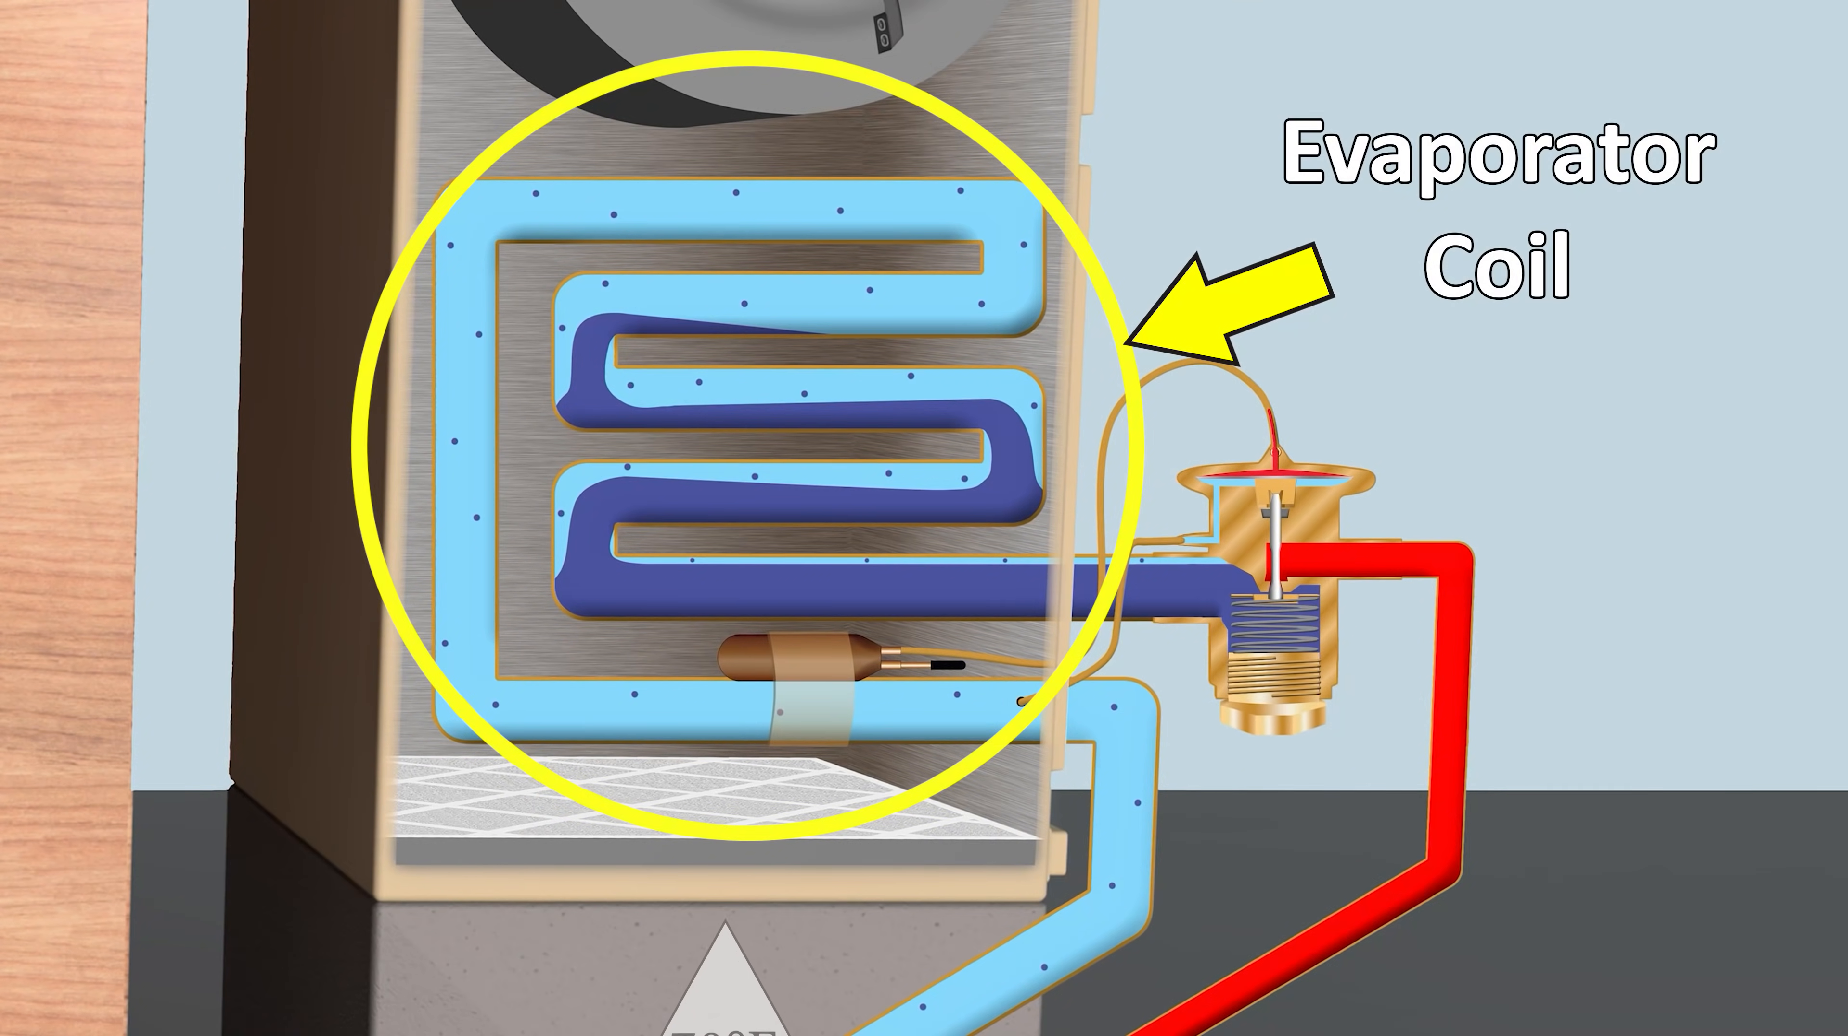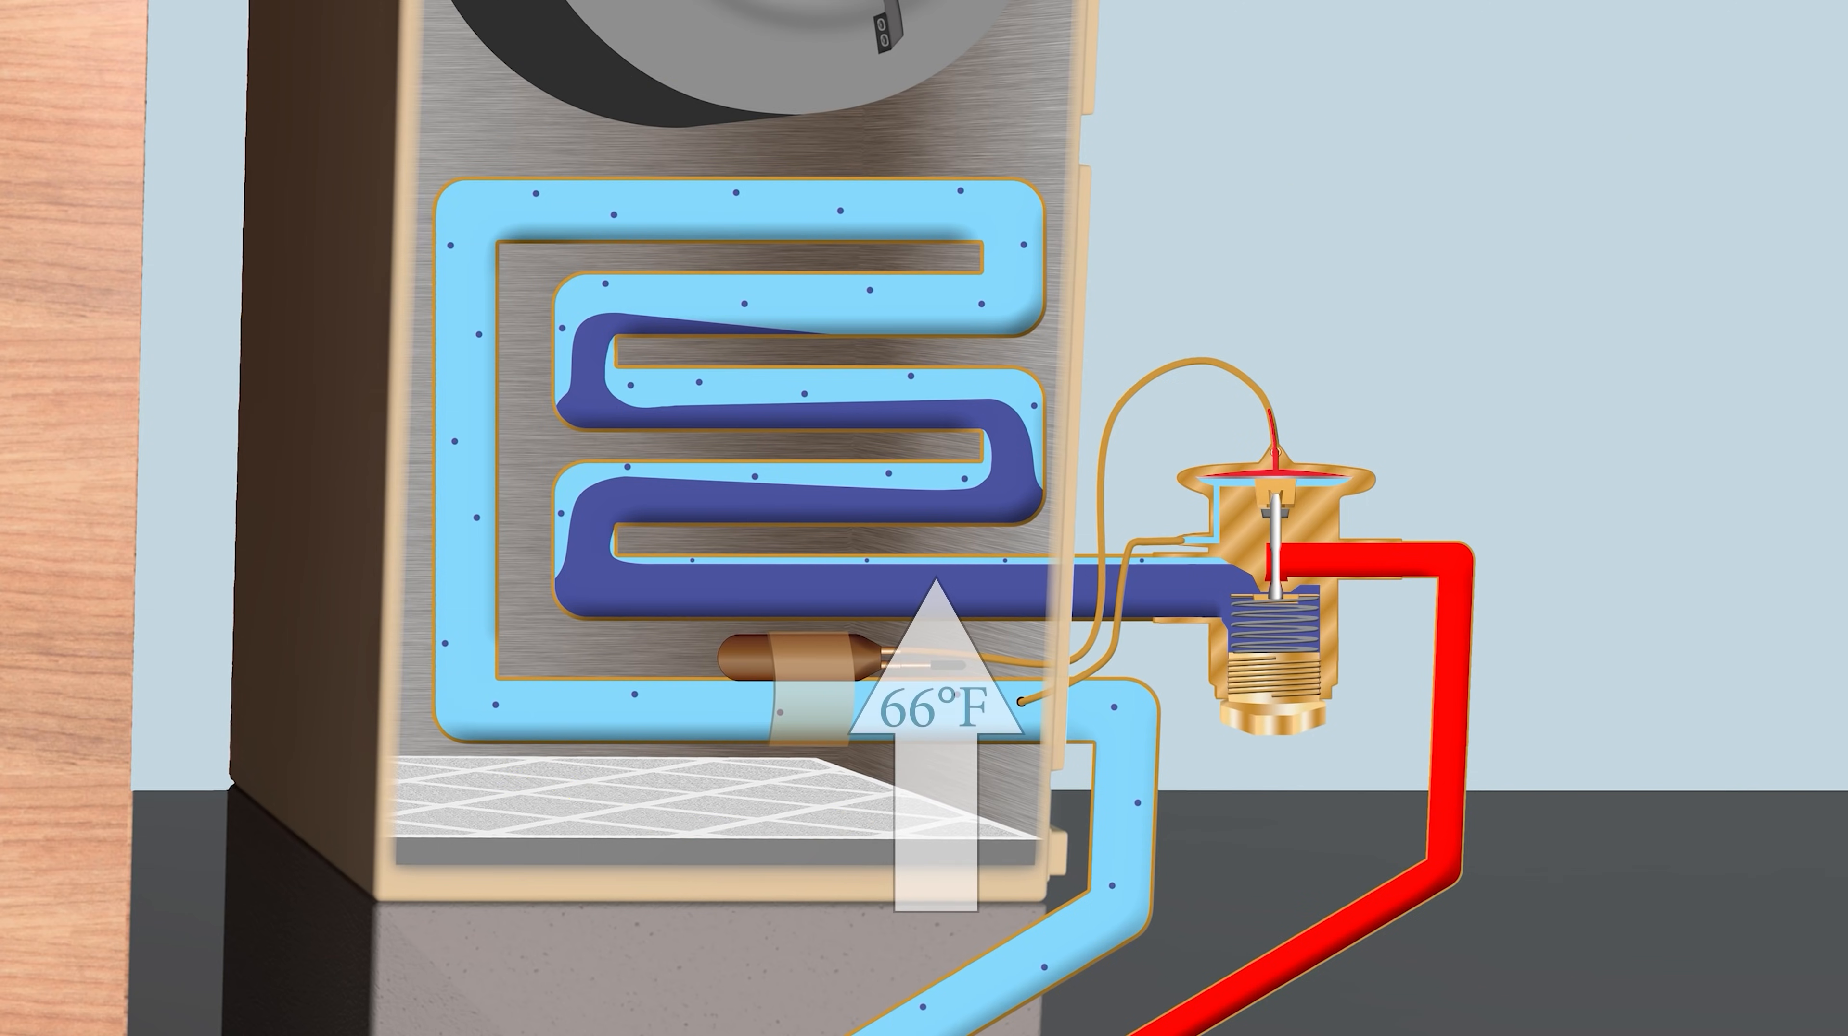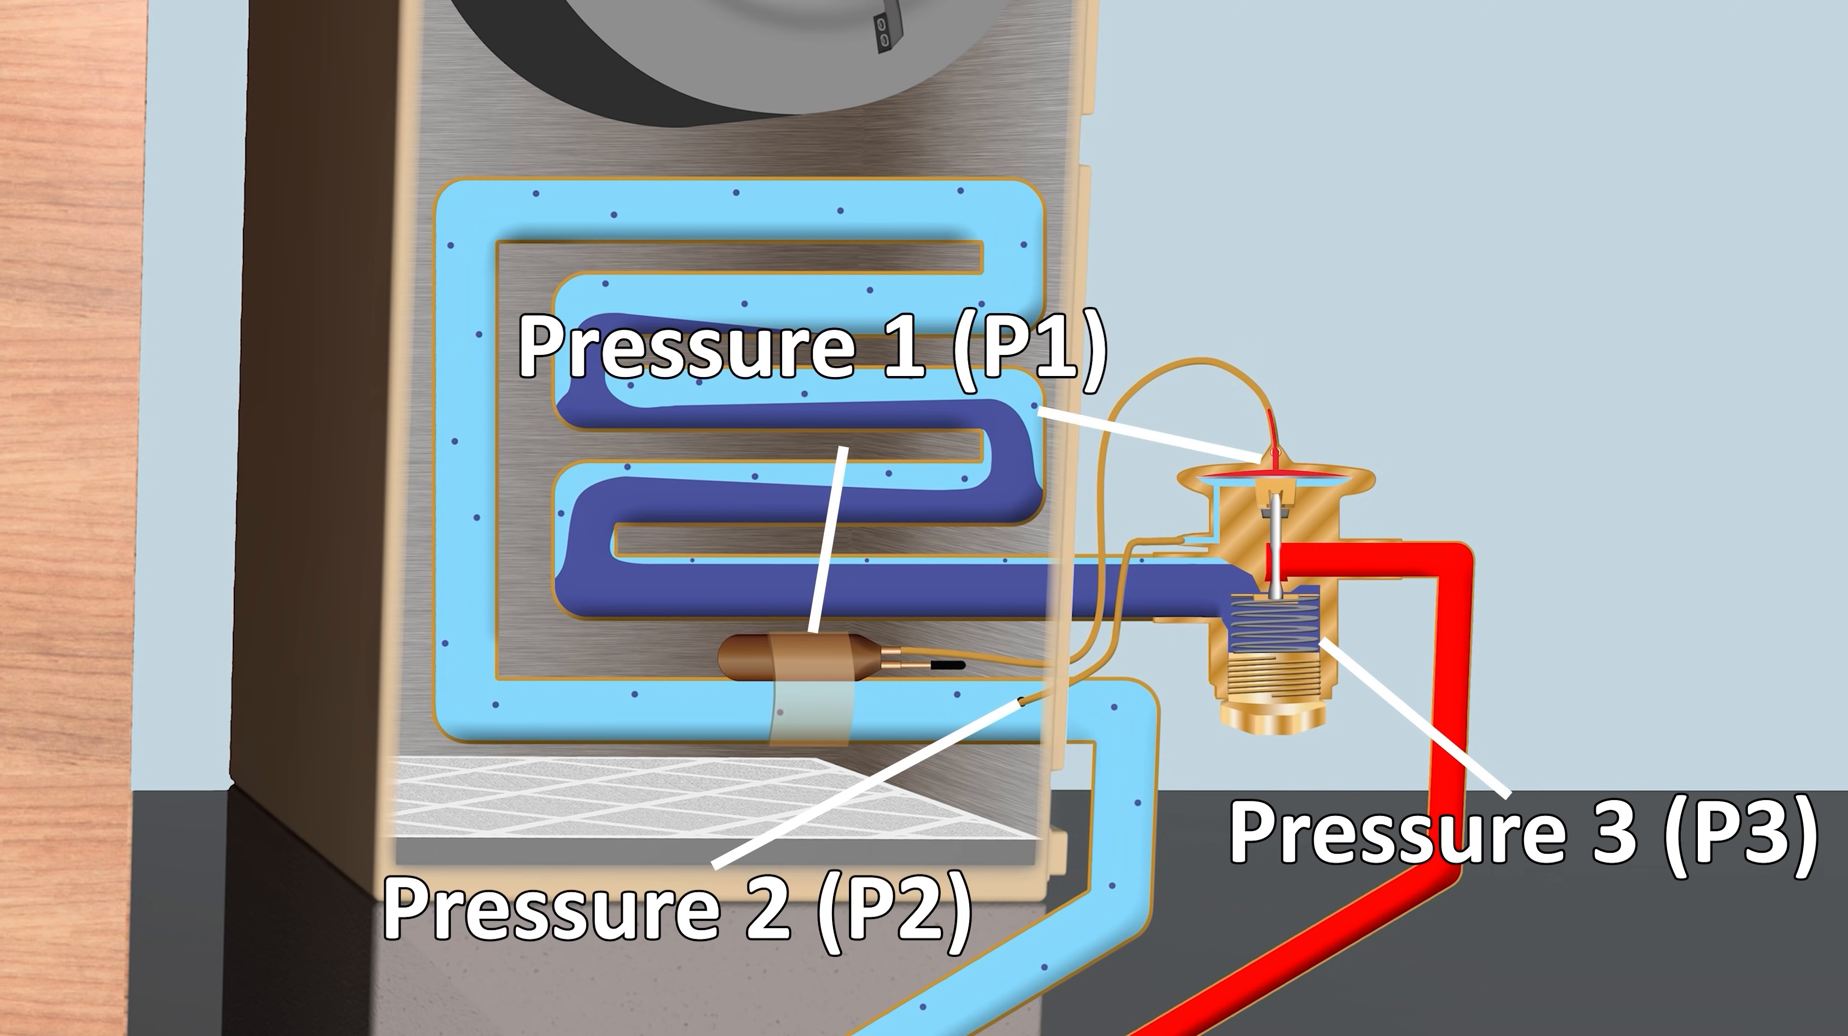You got to remember that we have heat that crosses the evaporator, so that's in the air, the airflow crossing the coil. The thermostatic expansion valve's job is to allow enough refrigerant into that coil to absorb the heat from the air. We have three pressures that are exerted on the thermostatic expansion valve in order for it to do its job.